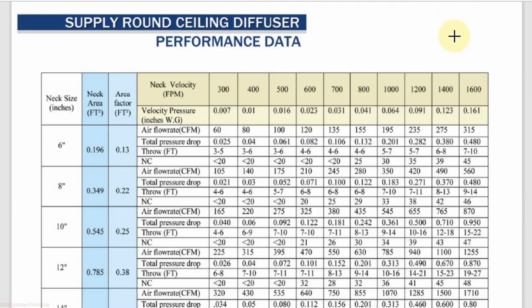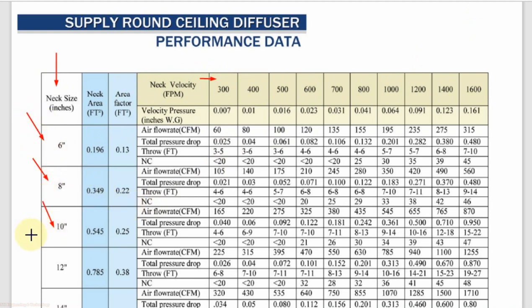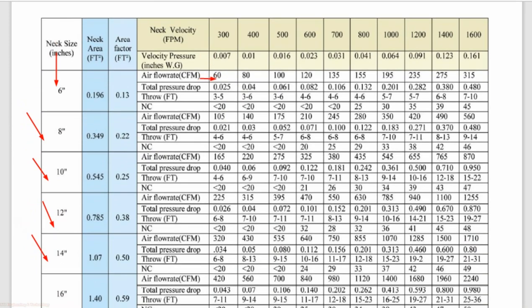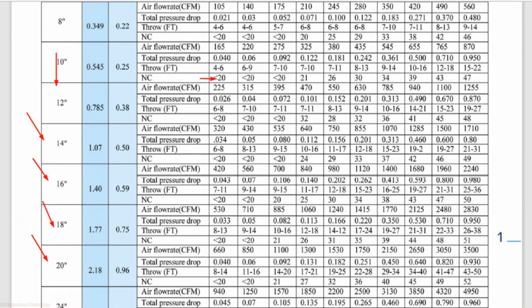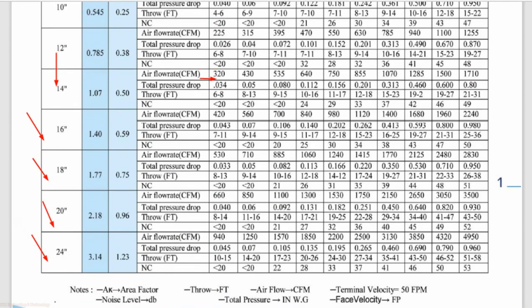To select the round ceiling diffuser, we use the performance data sheet provided by the manufacturer. In this sheet, the first column shows the neck size of the diffuser in inches, and the top row shows the neck velocity in FPM. The neck sizes available are 6 inch, 8 inch, 10 inch, 12 inch, 14 inch, 16 inch, 18 inch, 20 inch, and 24 inch.